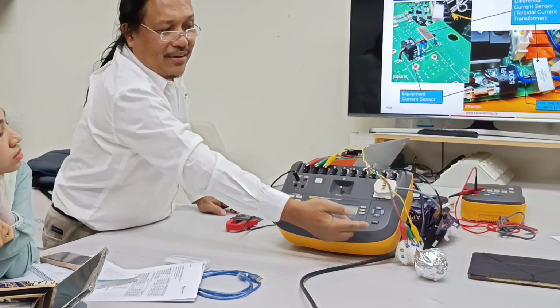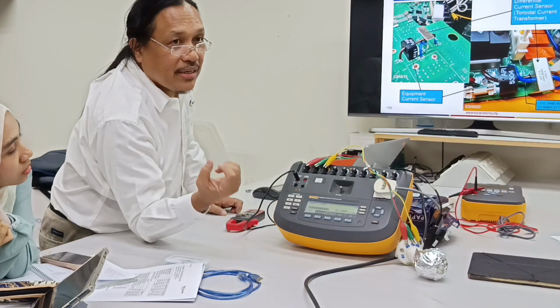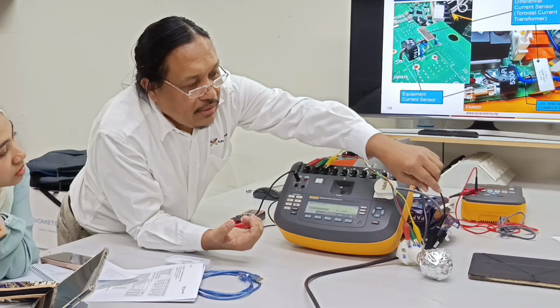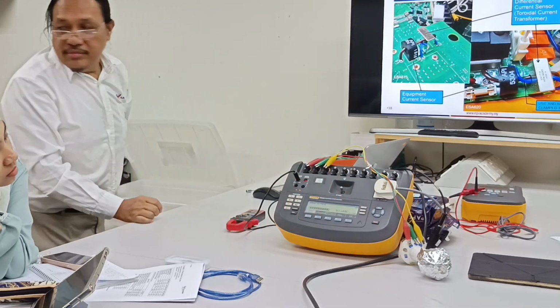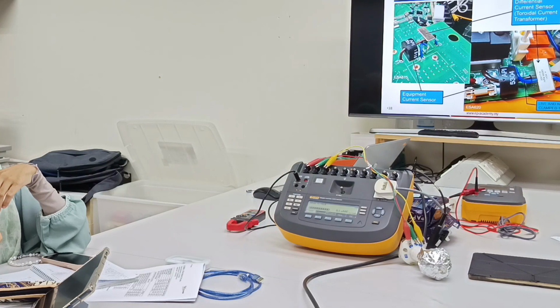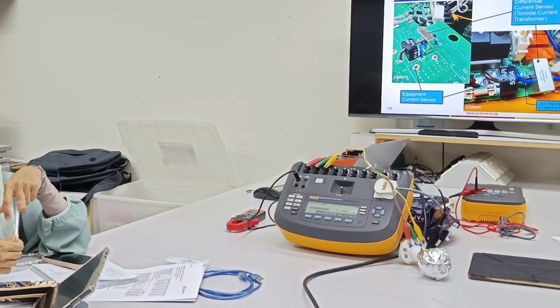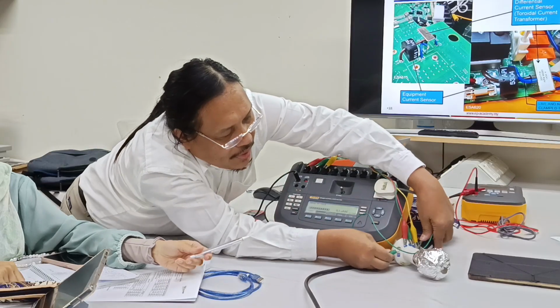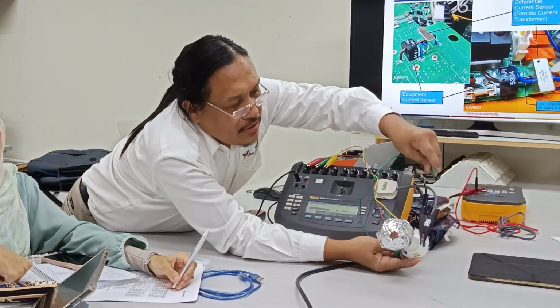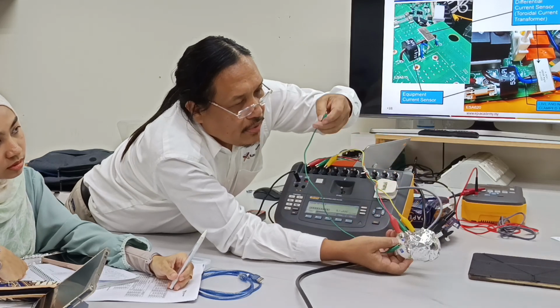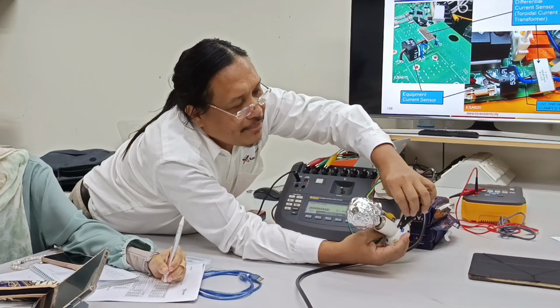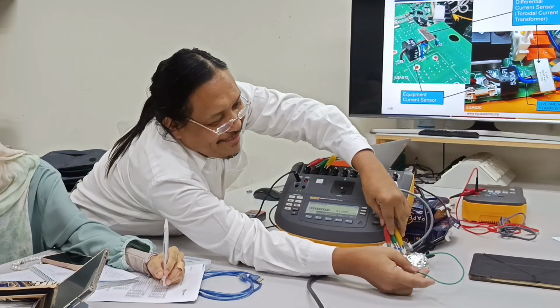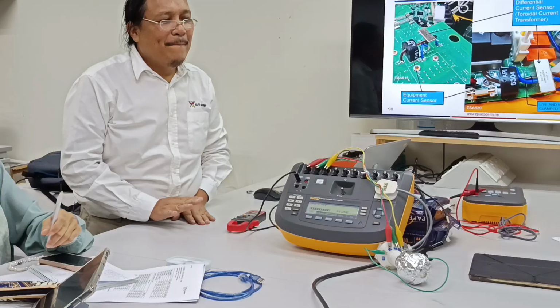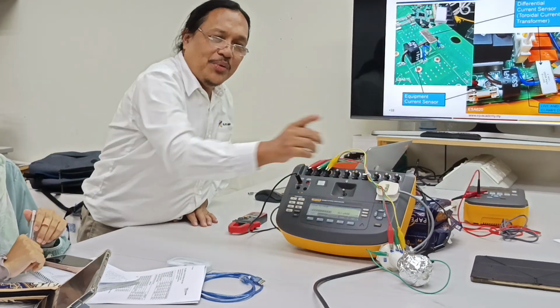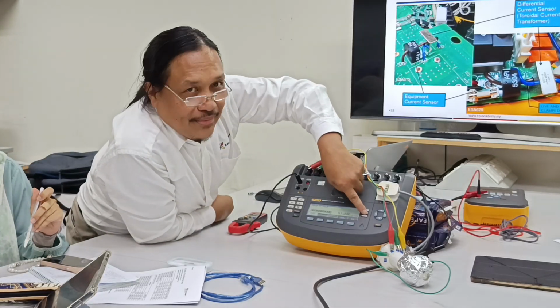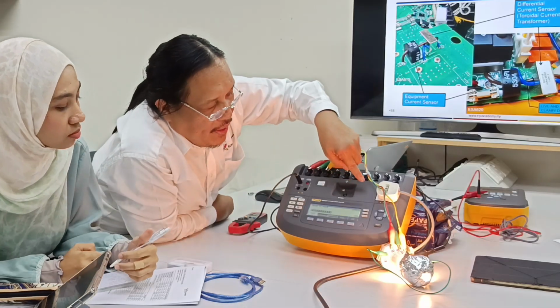But I must connect the non-earth because the non-earth is included in the equipment leakage. Equipment leakage has 3 leakages: applied part, earth, and non-earth. So I must connect the non-earth also.